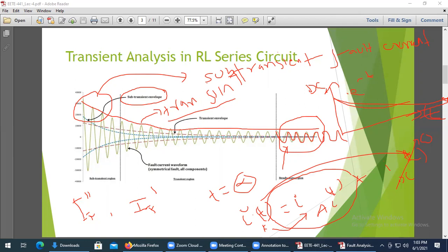So in a practical scenario, the circuit breaker or protective device trips within the transient period. We never achieve the steady state fault current, because we do not allow the fault current to flow up to that time. Before that, the protective device takes its action and operates. In the theoretical scenario, you will have three parts of the fault current: subtransient, transient, and steady state. But in practice, the steady state fault current is never achieved, because the protective devices clear the fault, stopping the fault current flow before the steady state period appears.